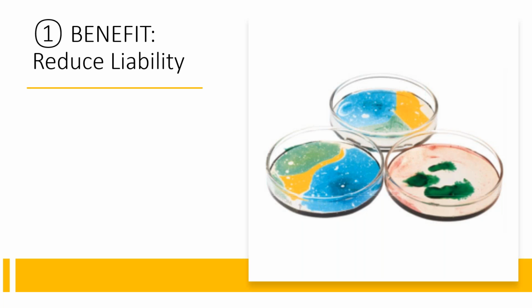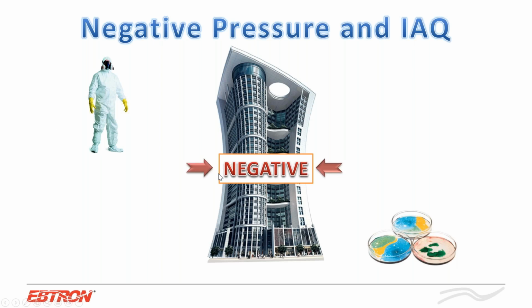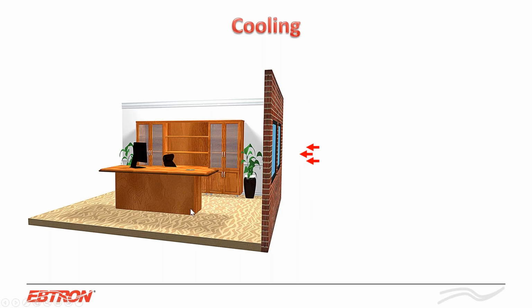And what they did to mitigate the issues with mold, right? And mold had already formed in there. But how can we try to eliminate any type of mold or fungal growth potential in the space with airflow measurement? So ultimately, like I was showing with the stack effect slide, we want to maintain our buildings to be slightly positive, because if they're slightly negative or negative, we are able to bring in unfiltered, untreated air through walls of the space, right? And what does that mean? Well, if it's a hot, humid day, you're bringing all that humidity in the space. You're going to have temperature control problems in your space, humidity control problems in your space. So we want to maintain the building to be slightly positive.